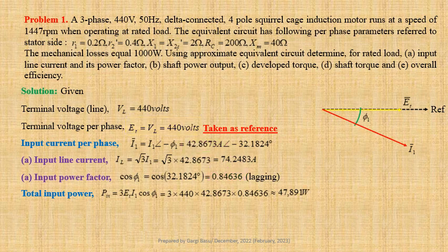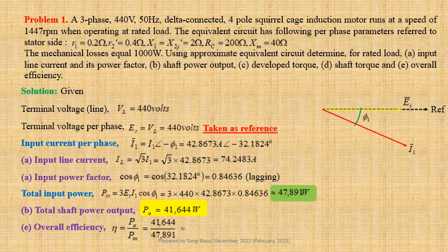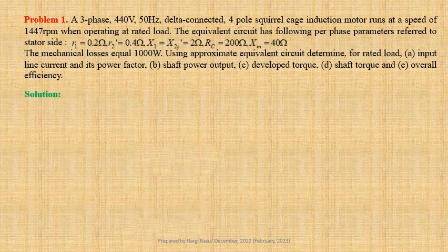Now we shall determine overall efficiency of the motor. η = Po / Pin. We have obtained total shaft power output Po = 41644 W. Therefore, η = 41644 / 47891 = 0.86956 per unit, or 86.956%.